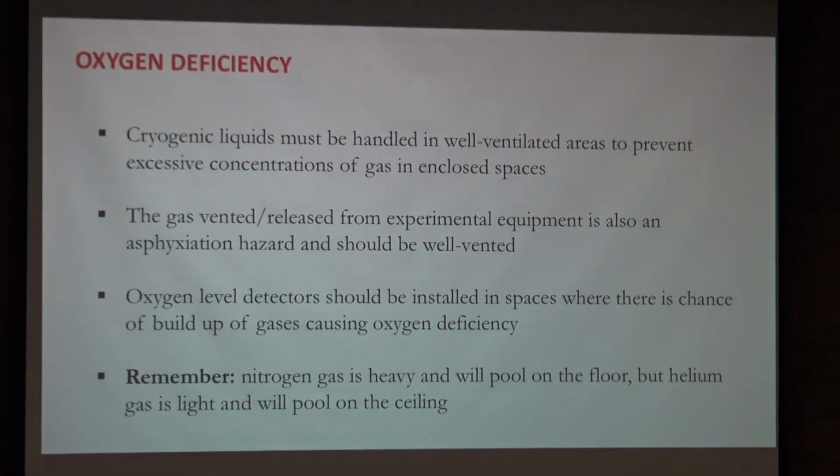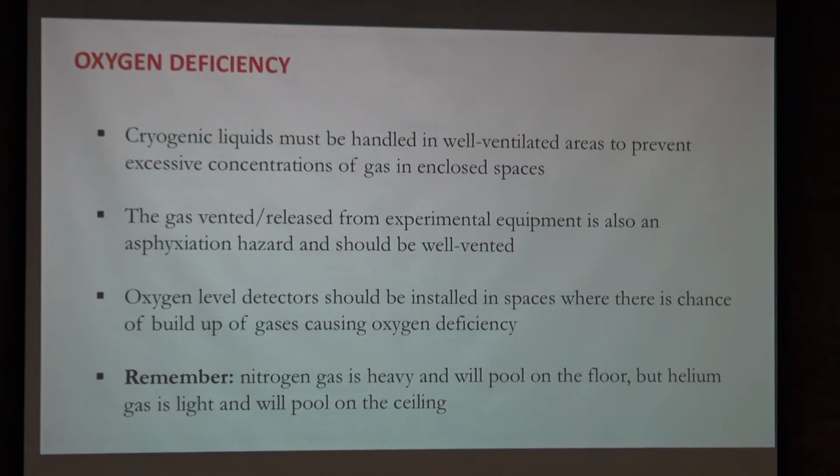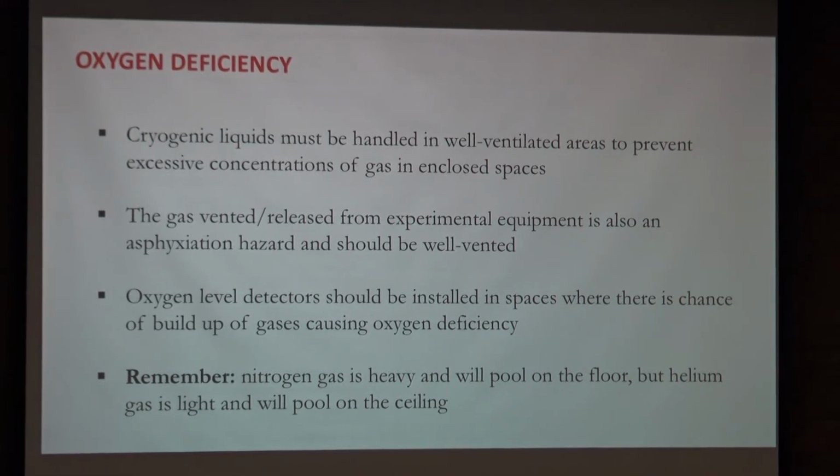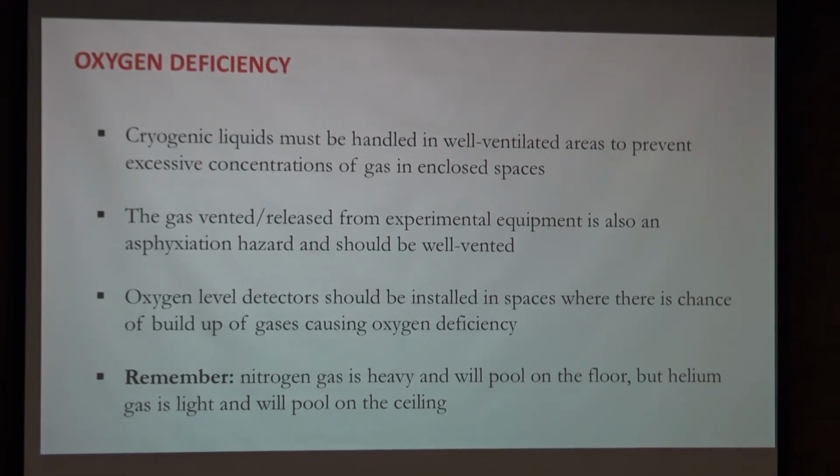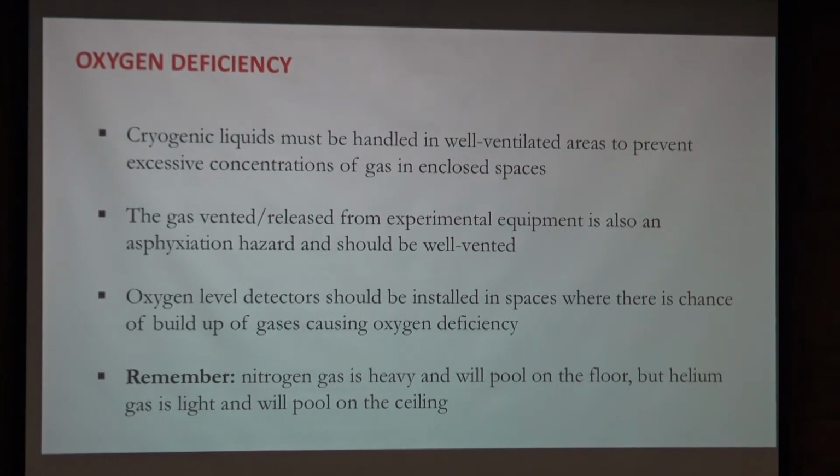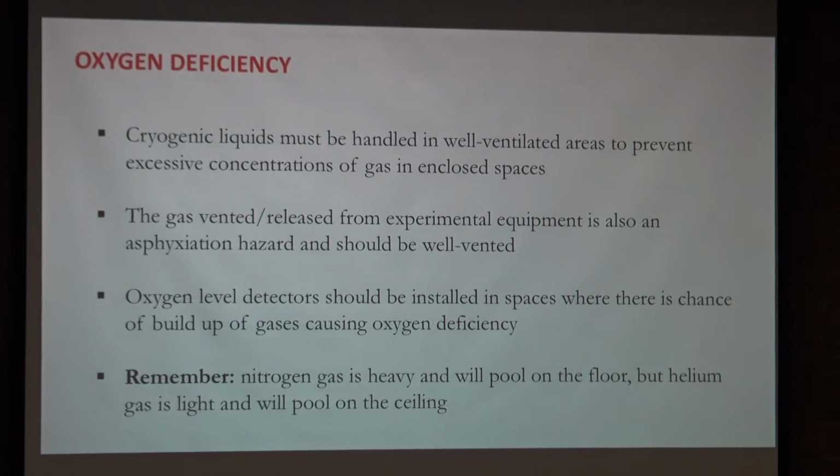That applies not only to the gas that evaporates from the fuel, but also gas that comes out of your cryostat or from whatever form of experimental setup you're using.